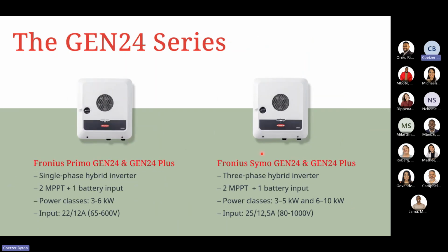So on the Gen 24 series, the Gen 24 comes in two different variations. So we have what we call the normal Gen 24 and Gen 24 Plus. So the Plus is referring to a hybrid inverter that you purchase out of the box, whereas the normal Gen 24 is referring to a normal grid tie unit that can be changed into a hybrid inverter later on when the client is needing to do so. So again, it's available as a single phase hybrid inverter. You got 2 MPPT DC inputs on the PV side, as well as one battery input also located on your DC connection points for your battery inputs.